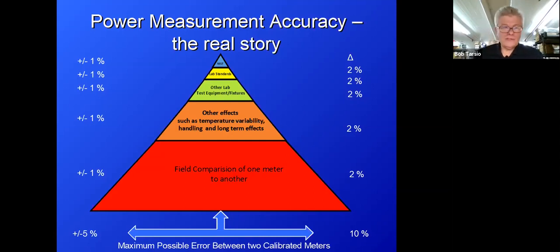We use another standard, which is basically a calibrated reference standard, which is nothing more than a signal generator that has an NIST traceable calibration. It basically says the level of that output of that calibrator is going to be within a certain percentage of error. And guess what that percentage of error is? Plus or minus 1%, about 0.05 dB. It's the same for calorimetry.